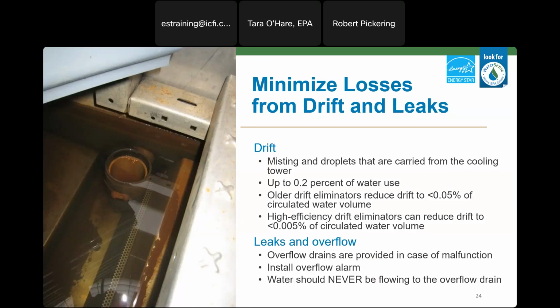Beyond water that is evaporated, some water can also be lost to drift or splash out. In a well-designed tower equipped with drift eliminators, this should really be minimal. However, if you're near your tower and you're noticing visible droplets that are exiting or pooling of water outside, this may be a sign that your drift eliminators need some attention. Drift eliminators can be added to an existing tower. You can also get higher efficiency drift eliminators to replace older, poor performing ones. They also have ancillary benefits, such as helping to reduce risk from Legionella or cooling tower water being sprayed in the outside environment.